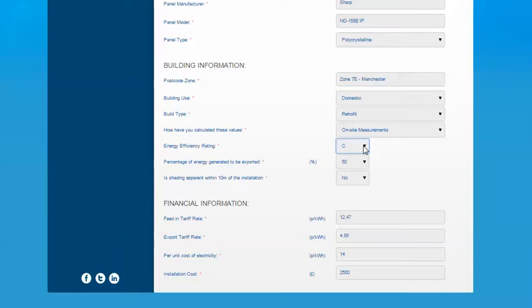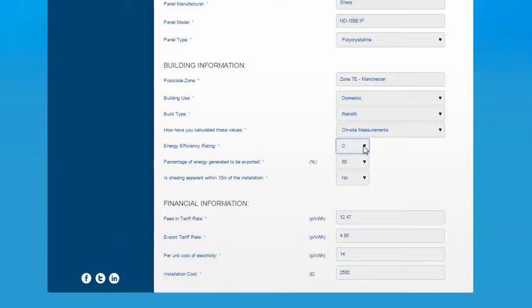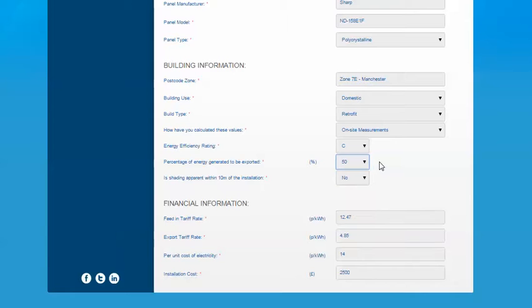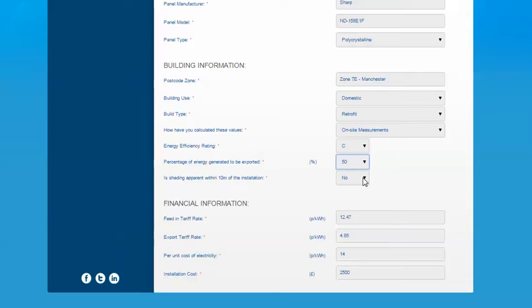You're then asked to state the amount of energy that will be exported. This is set to default to 50% because any install up to 30 kilowatts will be deemed a 50-50 split for the energy. However we've left this so you can edit it as it may be applicable for some larger commercial projects that more energy will be used either on site or exported. If it's a system below 30 kilowatts then it is deemed a 50-50 split. You then have a question about the shading and if there's any within 10 meters of the installation and that's just a simple yes or no answer.